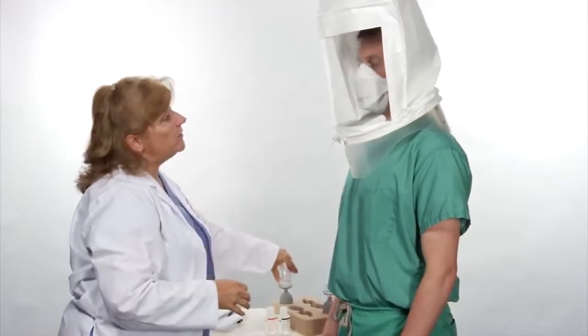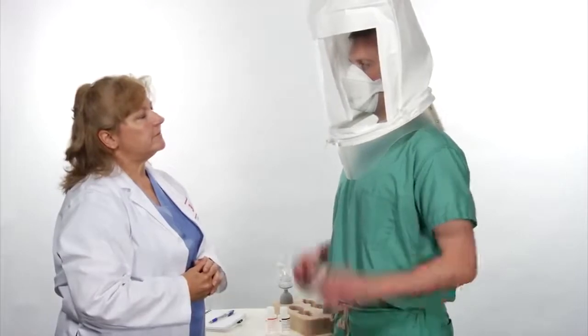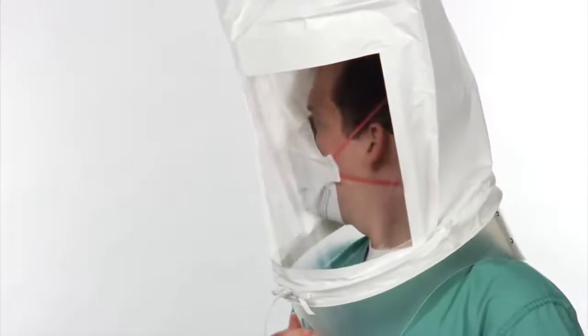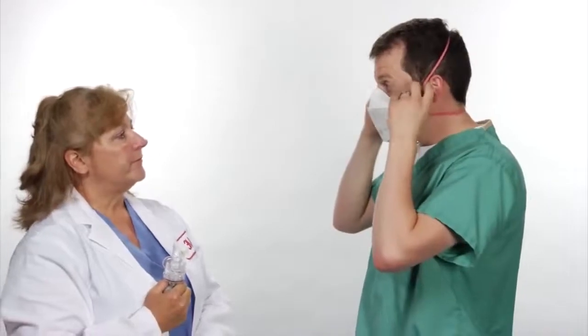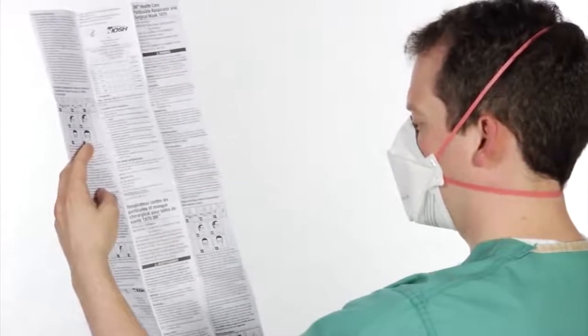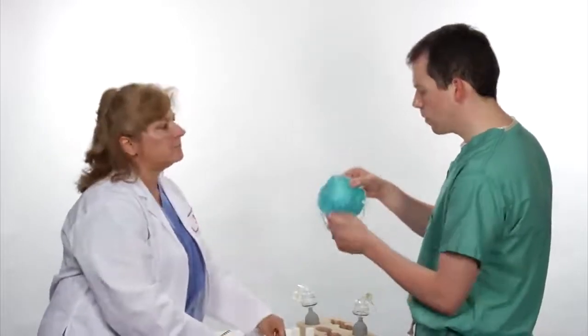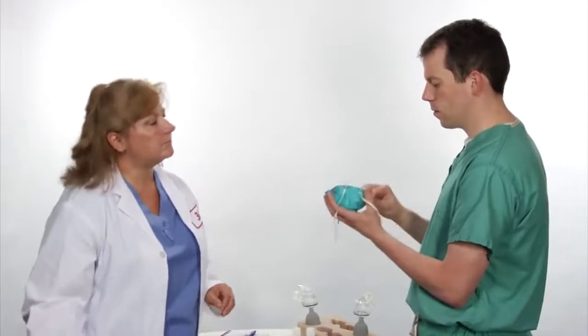If the fit test is completed without the subject detecting the sweet taste of the test solution, an adequate face seal has been demonstrated with the model of respirator. If the subject detects a sweet taste at any time during the fit test, an inadequate fit is indicated. Terminate the testing when this happens. Wait at least 15 minutes if you plan to re-test. Rinsing the mouth with water can help remove any lingering sweet taste. Ask the subject to review the donning instructions. Repeat the fit test after re-donning and readjusting the respirator. A second failure may indicate that a different size or model respirator is needed for that employee, such as another model of a 3M healthcare particulate respirator and surgical mask.